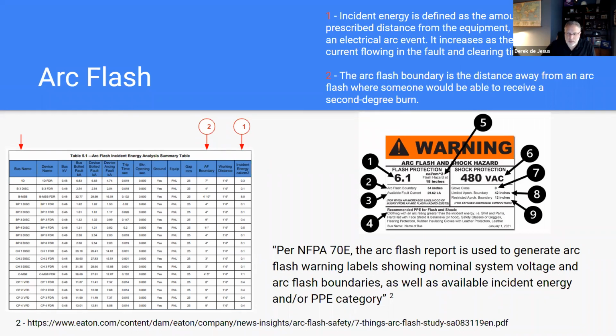All right, Tom says another note is that the SCCAF report many times has an incorrect trip unit for the breaker. Yep, completely agree. In other words, the breaker trip unit installed does not match the breaker trip unit that was used in the SCCAF report. Verify the trip unit and all the required information. Yeah, exactly. And sometimes it can be off by just a couple letters when it comes to the model number.